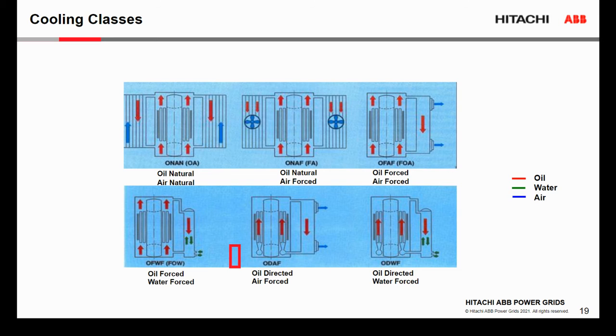Now we can look at the different cooling classes. So we have oil natural, air natural, very common in the smaller transformers. And this is, I would say, a maintenance-free solution. We don't have to really do any maintenance on it, or the maintenance is very limited. Then we have another solution where we want to improve the circulation of air around the transformer.